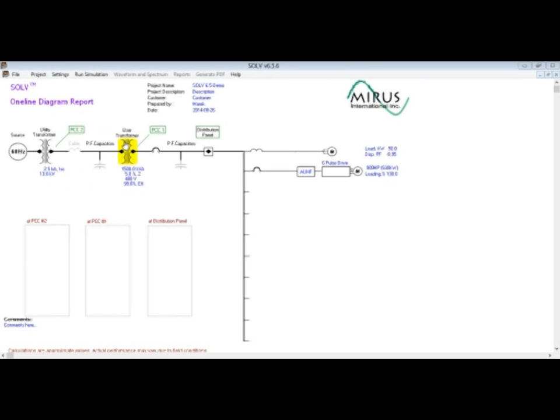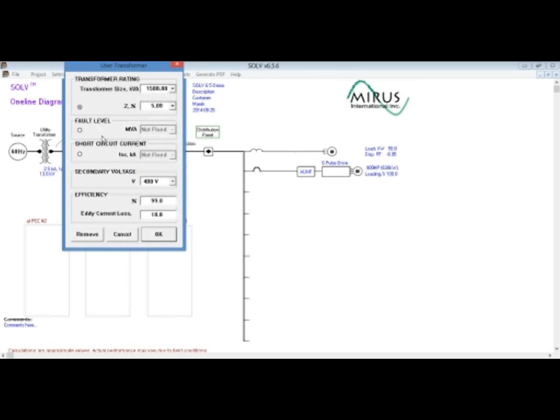Clicking on the user transformer brings up the dialog for the user transformer setup, and it's very similar to the utility transformer. So you can select the transformer in kVA and percent impedance, or fault level if that's unknown. Additionally, we have a section for efficiency and eddy current loss, that's in percent of the total losses for that particular transformer. Transformer efficiency is important for accurate energy analysis, so this is why we have this in this section.